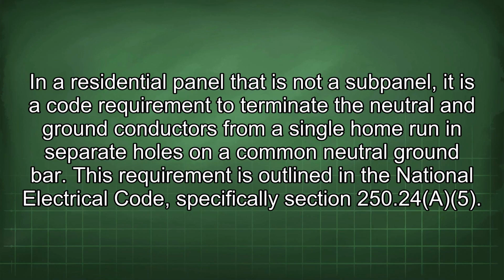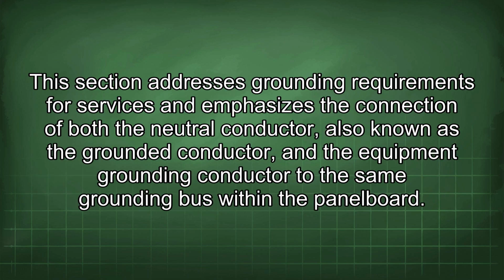In a residential panel that is not a subpanel, it is a code requirement to terminate the neutral and ground conductors from a single home run in separate holes on a common neutral ground bar. This requirement is outlined in the National Electrical Code, specifically section 250.24(A)(5). This section addresses grounding requirements for services and emphasizes the connection of both the neutral conductor, also known as the grounded conductor, and the equipment grounding conductor to the same grounding bus within the panel board.